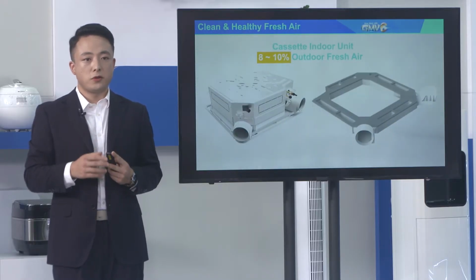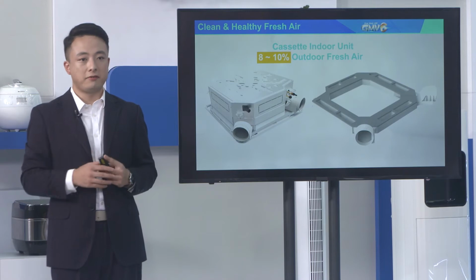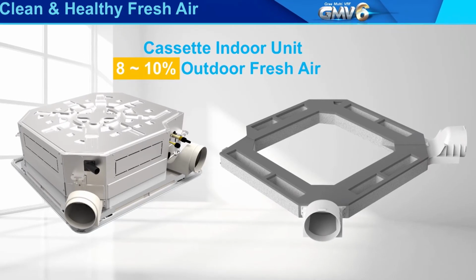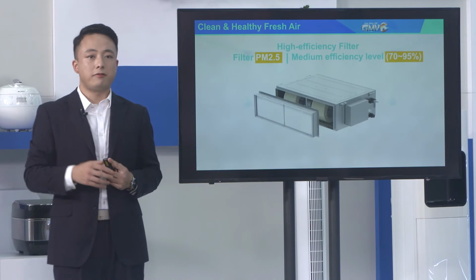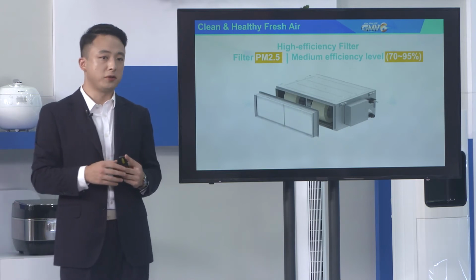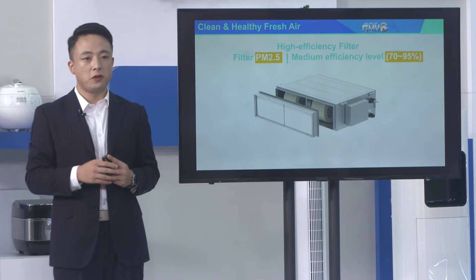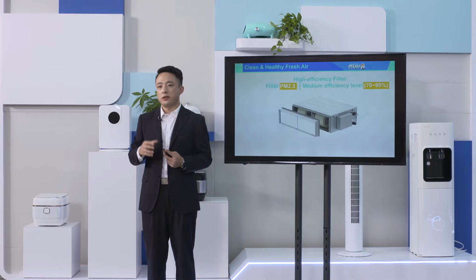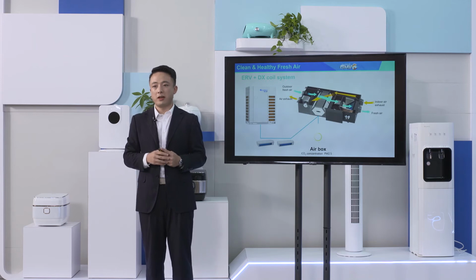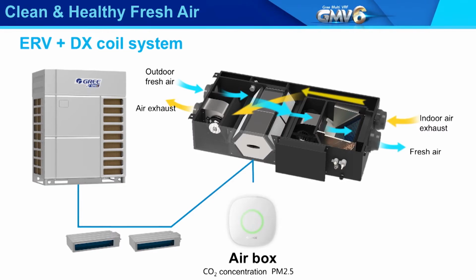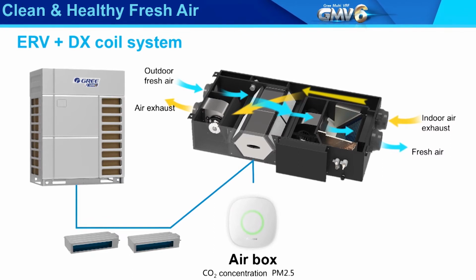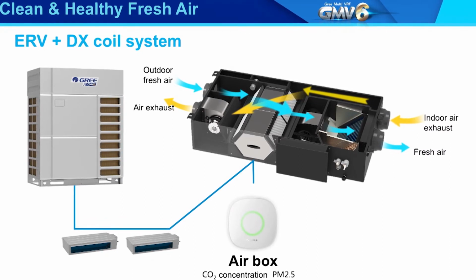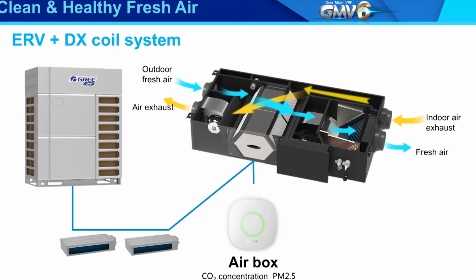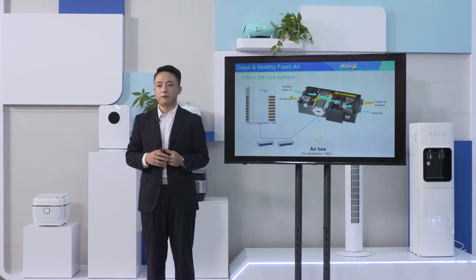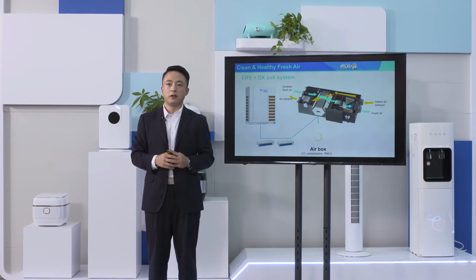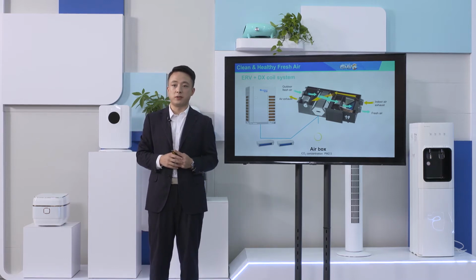The cassette-type indoor units with fresh air fittings can effectively introduce 8 to 10% fresh air. High-efficiency filter is available for the high static pressure duct type units, which can effectively remove PM 2.5. Energy recovery ventilation system is also available for GMV6. It can use a difference in airflow temperature for energy recovery during the introduction of outdoor fresh air and the discharge of indoor stale air. At the same time, the filter components purify the fresh air, creating a clean and healthy indoor environment.